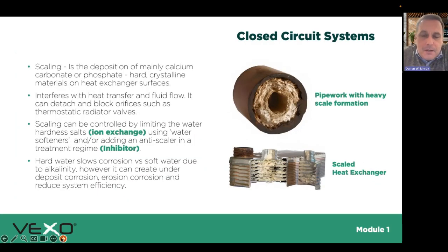So as I mentioned, there are various issues, starting with scale. In hard water areas, scale is a mineral that's in solution - it comes through when rain passes through bedrock, picks up minerals, and ends up in the water from our taps. If there's no pre-treatment before water goes into the closed system, and we're in a hard water area, we're going to introduce scale.